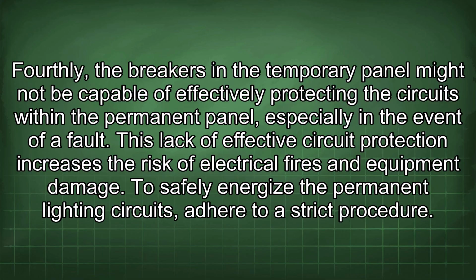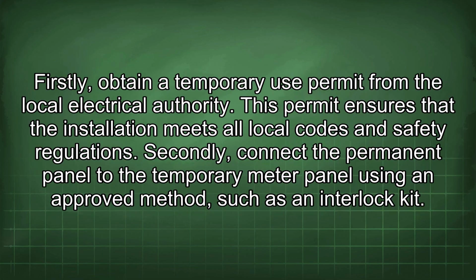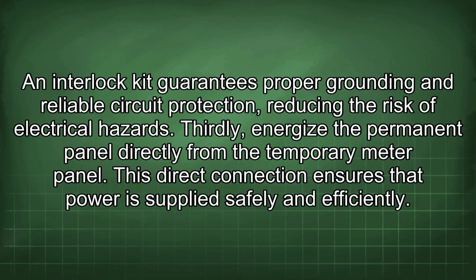To safely energize the permanent lighting circuits, adhere to a strict procedure. Firstly, obtain a temporary use permit from the local electrical authority. This permit ensures that the installation meets all local codes and safety regulations. Secondly, connect the permanent panel to the temporary meter panel using an approved method, such as an interlock kit. An interlock kit guarantees proper grounding and reliable circuit protection, reducing the risk of electrical hazards.